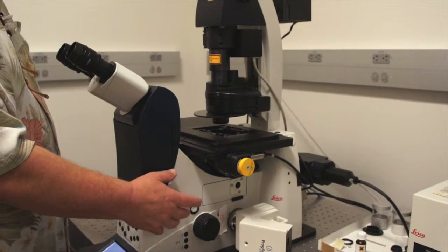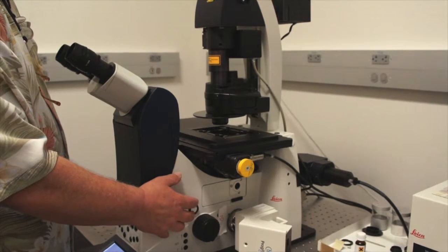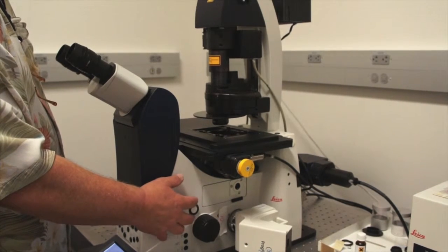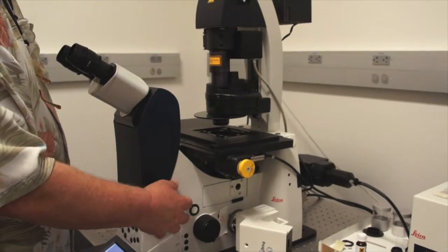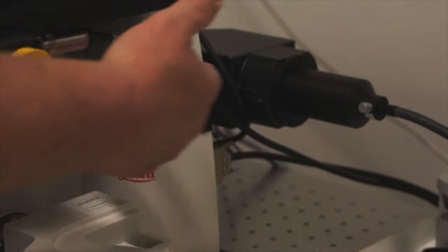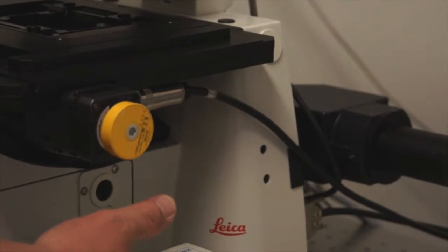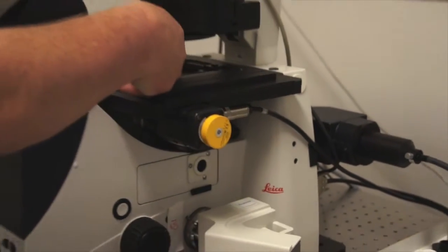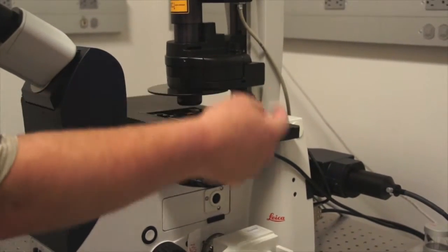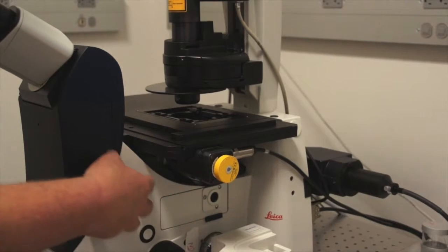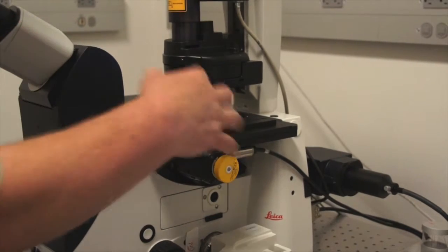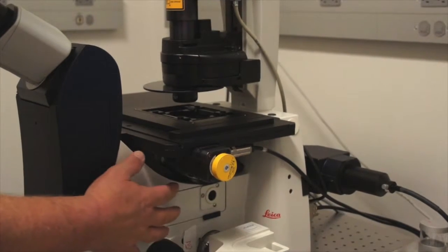We discussed epi-illumination, which is light from above for the fluorescence microscopy application. Here we have an illuminator which is supplying the fluorescent light, and again it comes in below the stage. It is epi in that it does come through the optics and reflects off the specimen and back down through the optics and then transmitted into the microscope. But it is reversed because this is an inverted microscope.